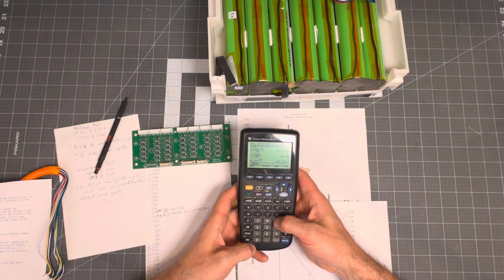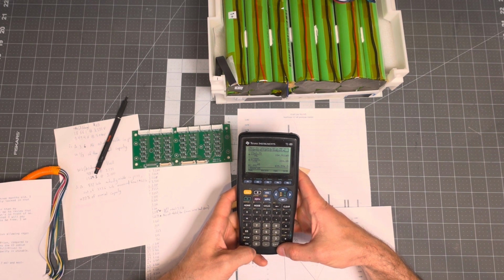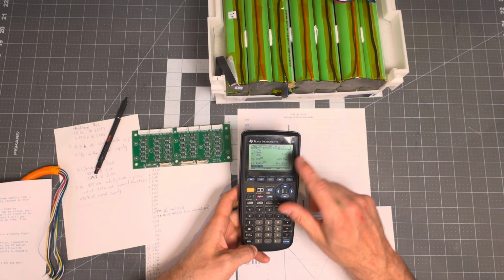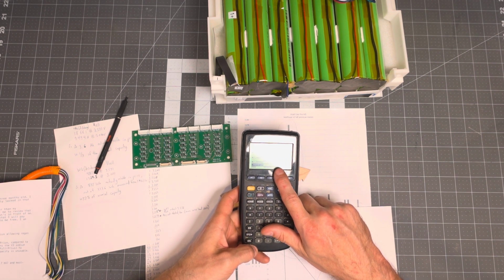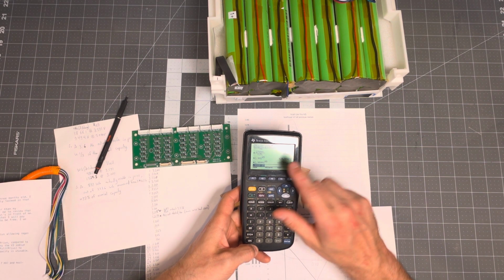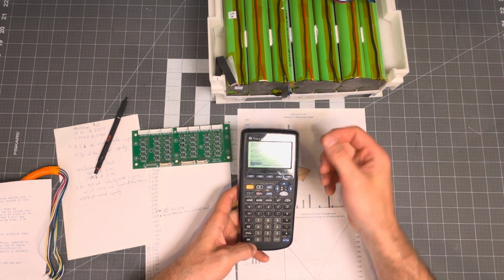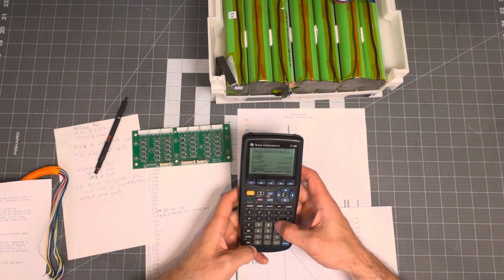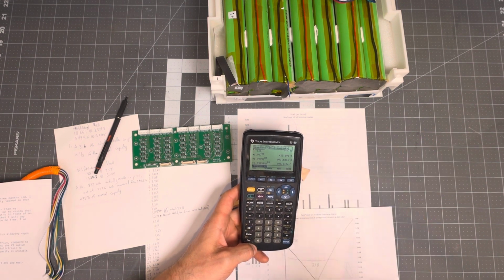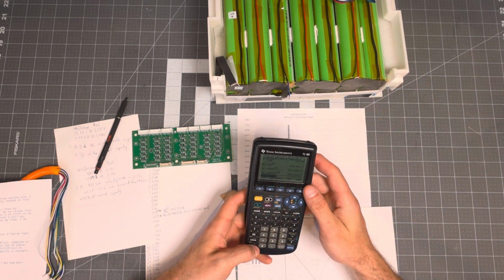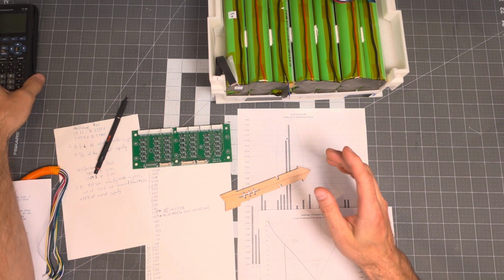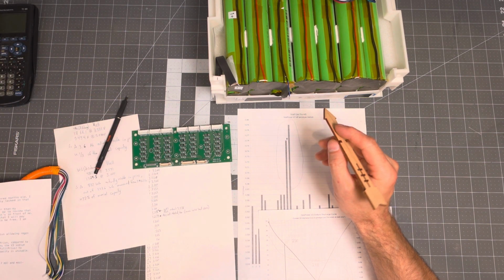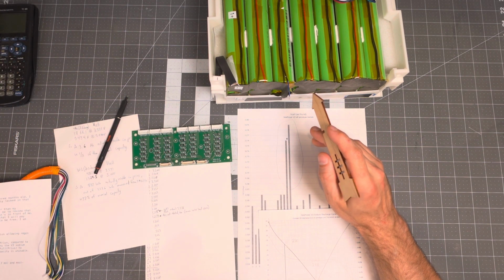And even if we increase this to 99.99% effectiveness, we still have a 1% risk of failure per pack that one of these cells is going to come disconnected. That's pretty high. Even if you go out to the 5 nines, at 5 nines, you only have 1 in 1,000. But we're not, that was 6 nines. At 6 nines, we're not getting out there. This is not a Six Sigma product by any means.